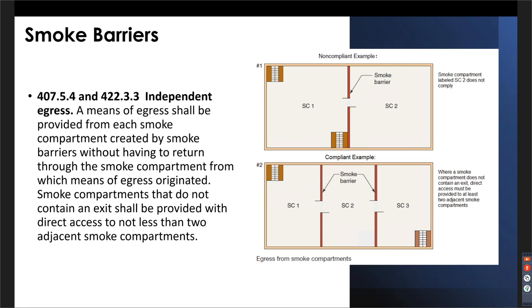adjacent smoke compartments. So if you look at the example on the top, that's a non-compliant example. That smoke compartment number 2 does not have its own exit. And if there were a fire in smoke compartment 1 and everybody was relocated to smoke compartment 2, they're kind of not in a good spot, right? There's no way out. So on the bottom example, smoke compartment 2 still doesn't have its own exit, but it now has the required access to 2 adjacent smoke compartments, and each of those have their own exit. You don't want to create a dead-end condition. So it's not new in practice, it's just clearer in the code to have that.